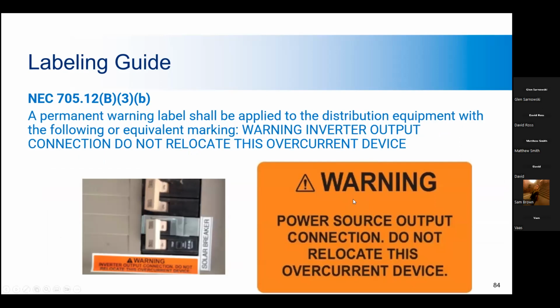This is for a backfeed breaker. It's a power source output connection label. It specifies that these breakers should not be relocated because they typically, as I mentioned earlier, are on the opposite side of the panel as the main disconnect.